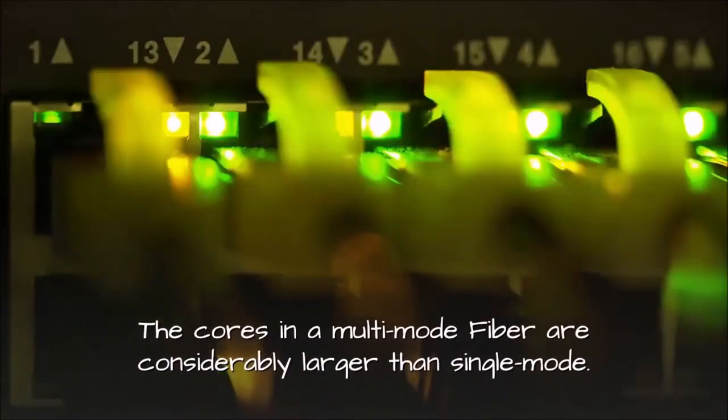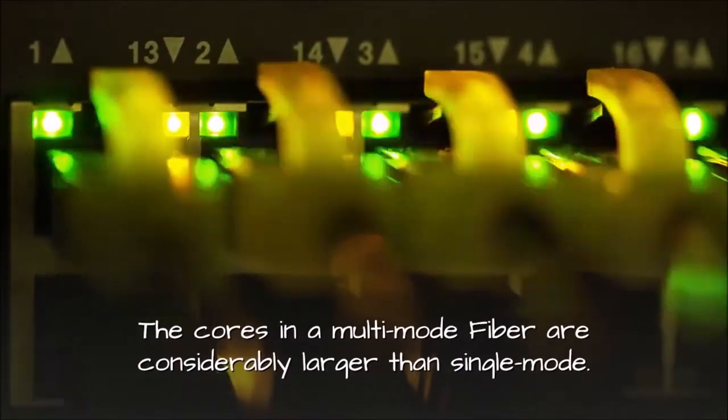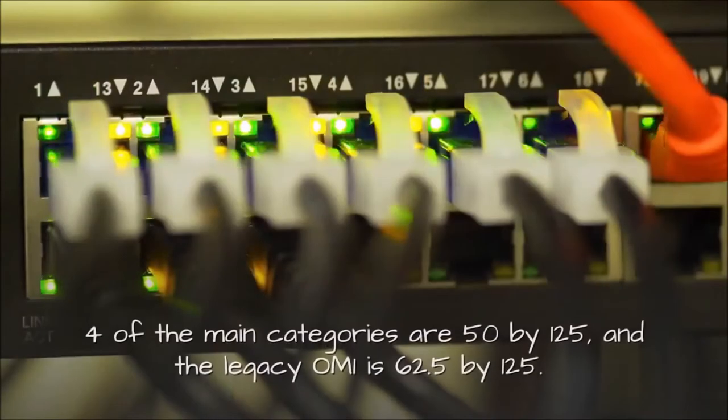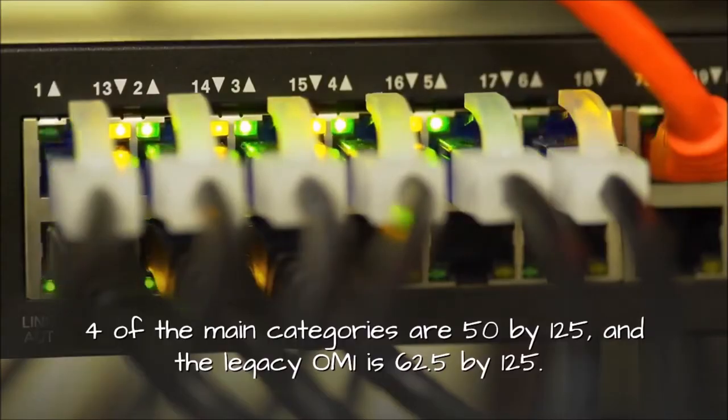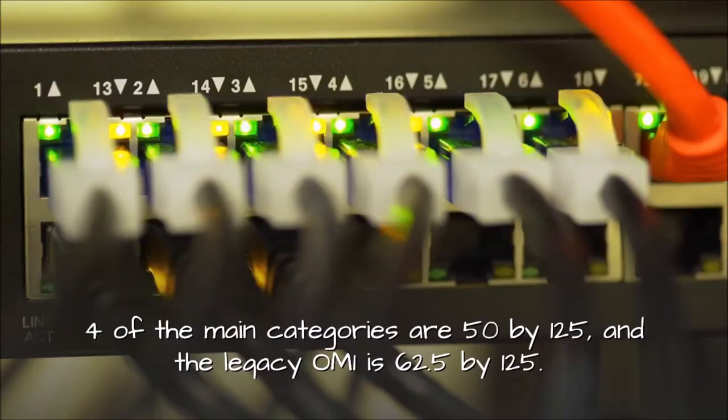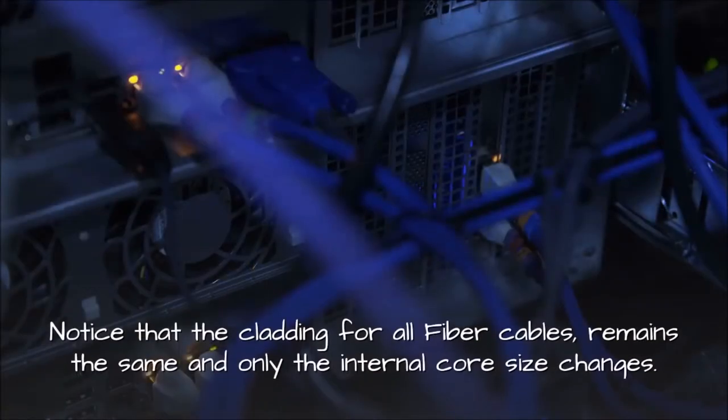The cores in a multimode fiber are considerably larger than single mode. Four of the main categories are 50 by 125, and the legacy OM1 is 62.5 by 125. Notice that the cladding for all fiber cables remains the same and only the internal core size changes.